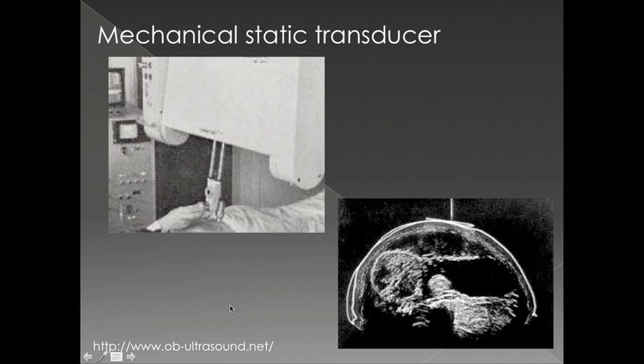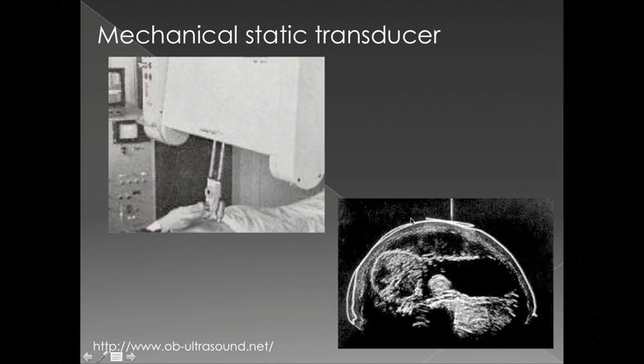You have to have some way to organize these different sound waves and actually be able to produce an image. Originally what they had was called a mechanical static transducer, where you actually had a gantry with a single piezoelectric crystal transducer mounted on it that scanned across the patient in order to get physical data about where a particular sound wave was with respect to the patient. That's how the individual beam lines were actually organized into an image.